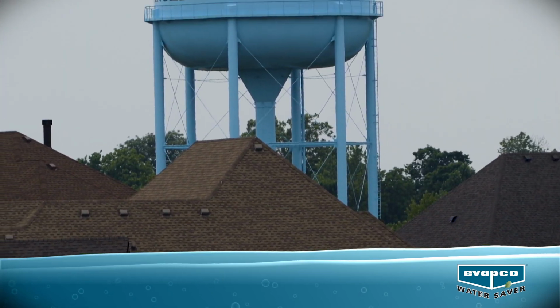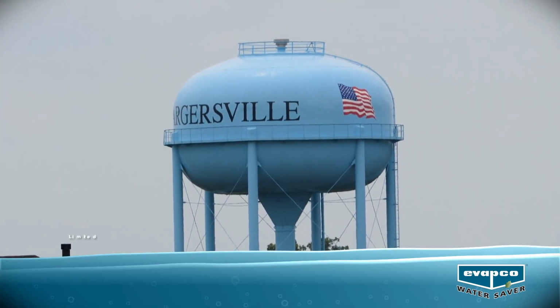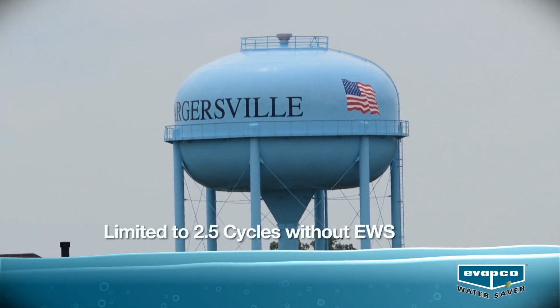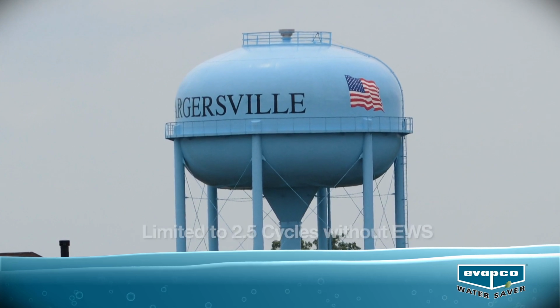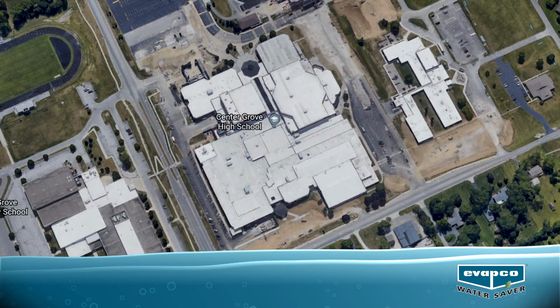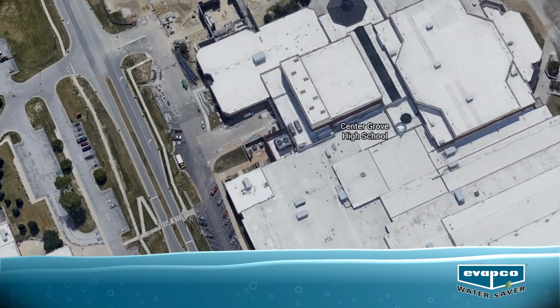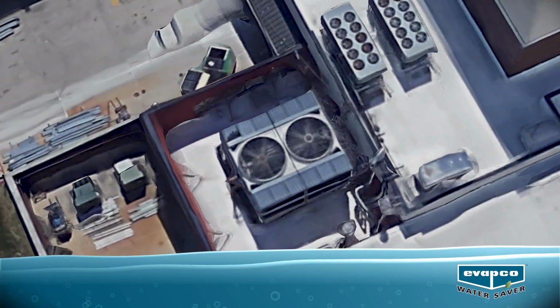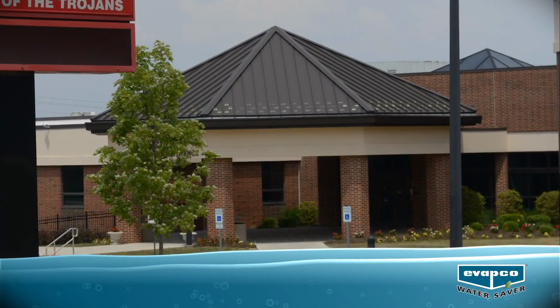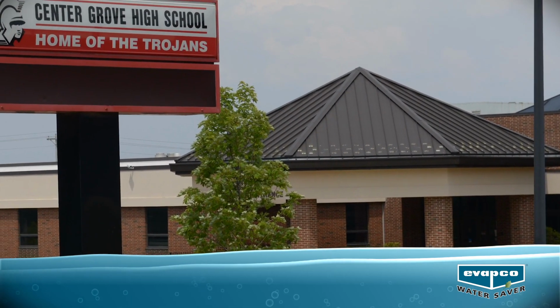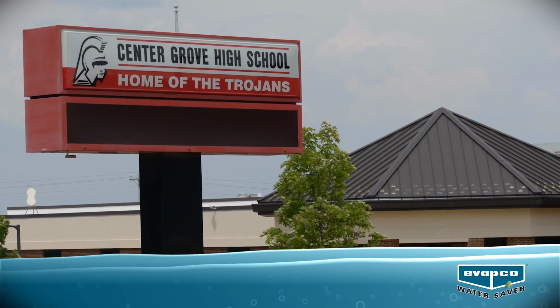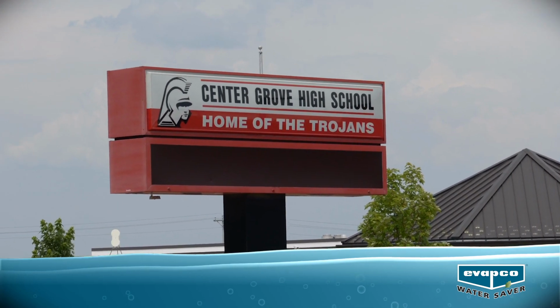My name is Daryl Thompson. I'm the Director of Facilities for the Center Grove Community School Corporation, located south of Indianapolis. Our groundwater source for the tower makeup is naturally scale forming, which limits the cycles of concentration to about 2.5. We recently replaced the cooling tower on our high school, which operates year-round. One of the goals for the project was to make it easier to achieve consistent water treatment results, which would reduce the maintenance and maximize the life of the new tower.